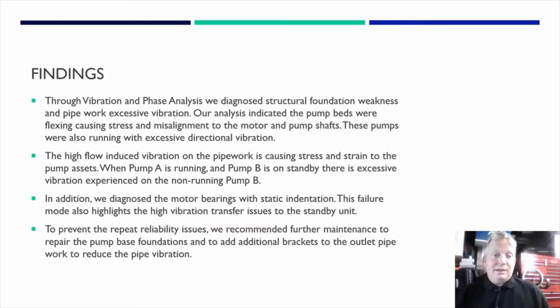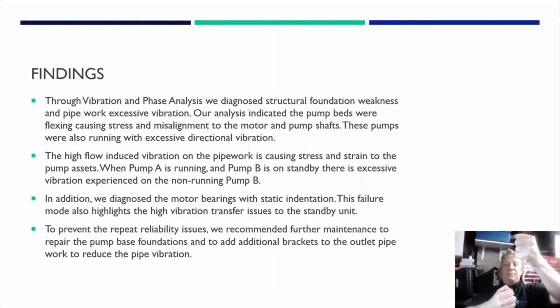So, vibration analysis and phase, because what we did on this, because you've got a motor, you can basically put two transducers and do cross channel phase. And if you put a transducer there and a transducer there, it should be zero phase movement. But if you put a transducer on that and then a transducer on the bed frame, and you watch your phase, as your phase changes, it would mean it's pulling apart. So you can mentally get a picture, so you can map out the movement, so we can determine what the pump and base is doing. So we could say, well, the root cause of all your motor bearing failures, your pipe cracking, your flanges going, is because the base is too weak.